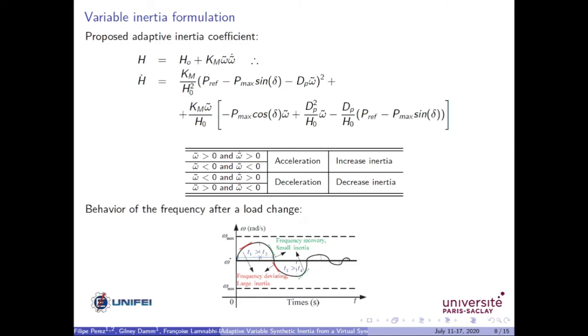This idea can be summarized in this table, where when we have same signs for frequency deviation and its derivative, the machine is in acceleration process, which means that the angular speed is deviating from the original value. Therefore, the inertia should increase to minimize frequency deviation. And when we have different signs of frequency deviation and its derivative, the machine is in decelerating process. So when the inertia is decreased, we may allow to return faster to the new equilibrium point.